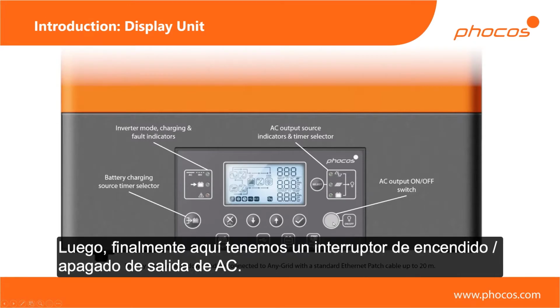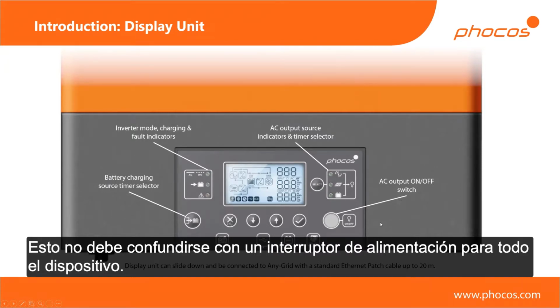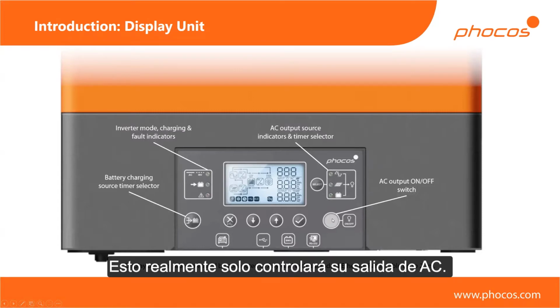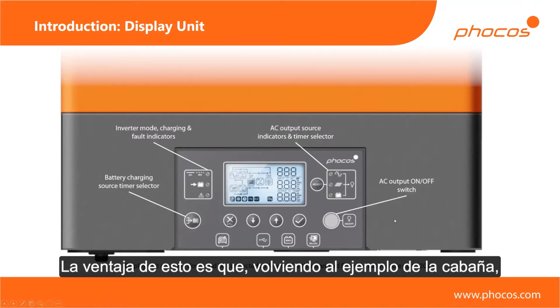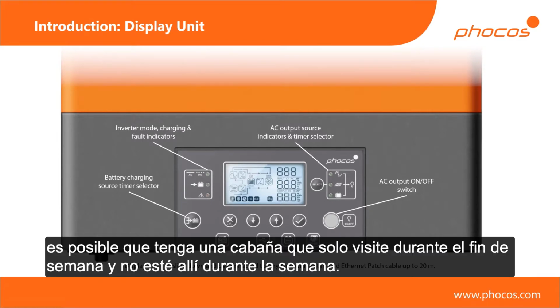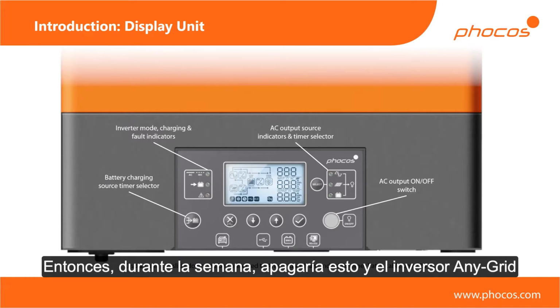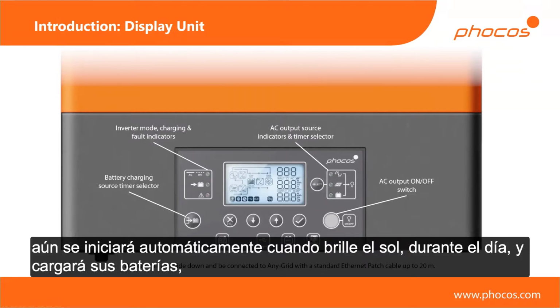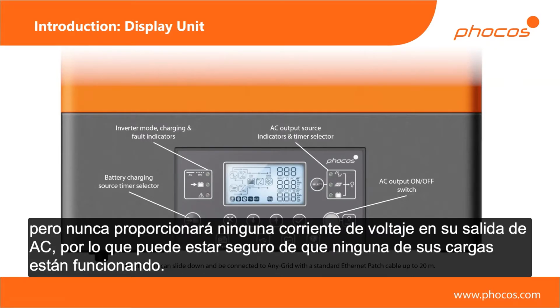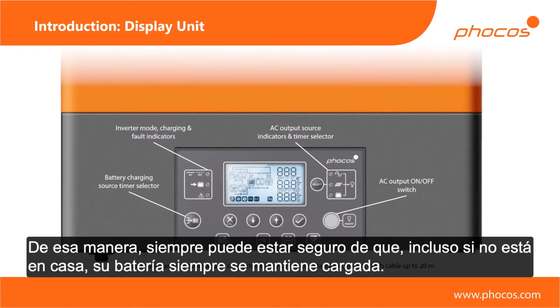And then finally, here you have an AC output on-off switch. Now, this is not to be mistaken for a power switch for the whole device. This will really only control your AC output. The advantage of that is if, for example, getting back to the cottage example, you might have a cottage which you only visit during the weekend and you're not there during the week. Well, then during the week, you would turn this off, and the unit, the Any-Grid, will start up automatically when the sun is shining, so during the day, and it will charge your batteries. But it will never provide any current or voltage on your AC output, so you can be sure that none of your loads are running. But like that, you can always be sure that even if you're not home, your battery is always kept topped up.